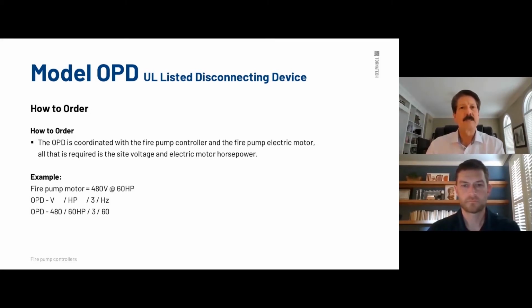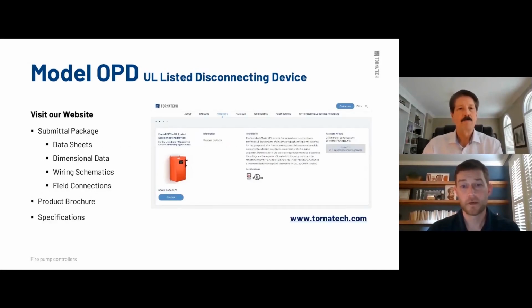One of the biggest things I found dealing with utility companies in presenting this product as an alternative for them is they come up and say, we've had so many situations in the past week or two where the electrician really isn't familiar and knowing how they need to size that disconnect. And it could cause a problem because you don't want that disconnect to trip offline. That's not the intent of it. Right. Or they could oversize it so much and make it a lot more expensive. So that is definitely the benefit for us doing the work there, matching the horsepowers. Exactly. Again, this tells it all. Our website has submittal packages, data sheets, dimensional, schematics, field connections, specifications for engineering. Now, again, the value add that this brings is tremendous.